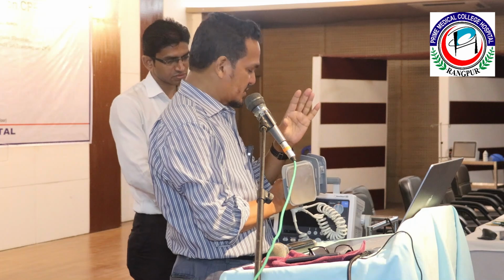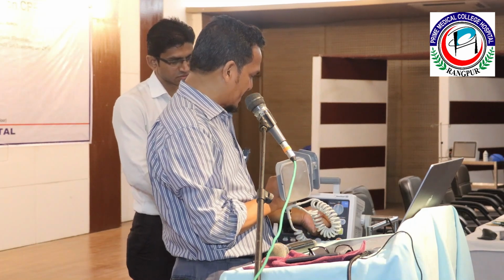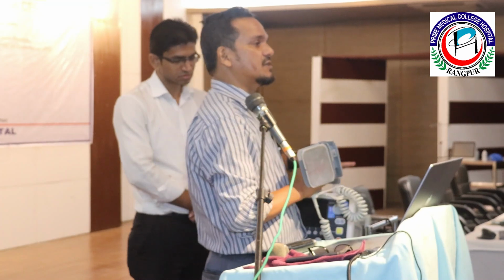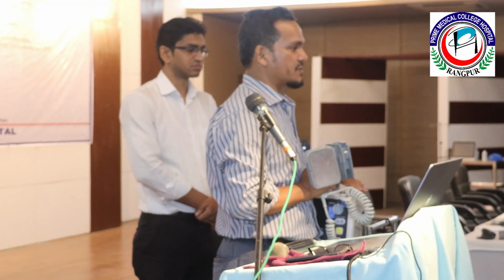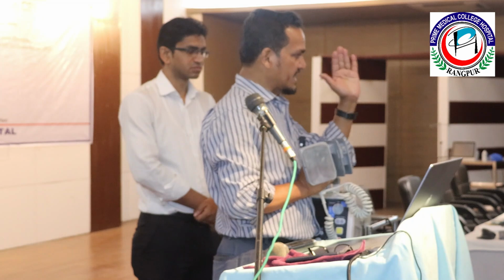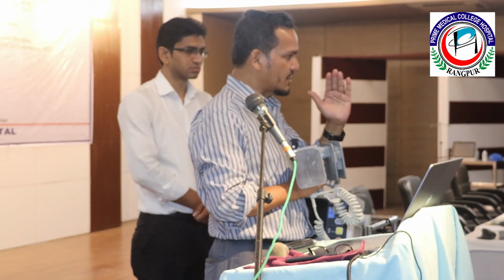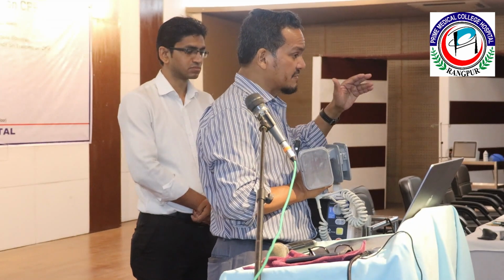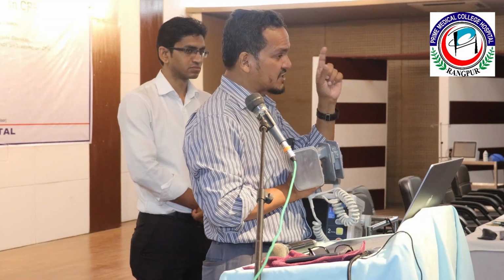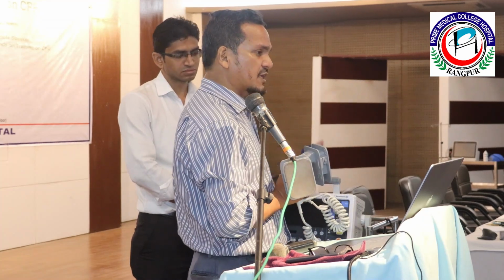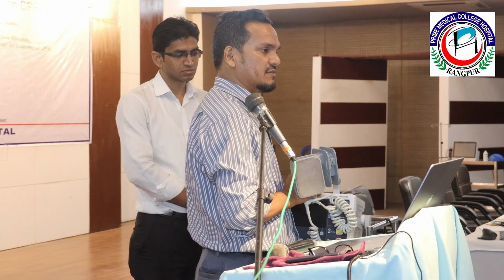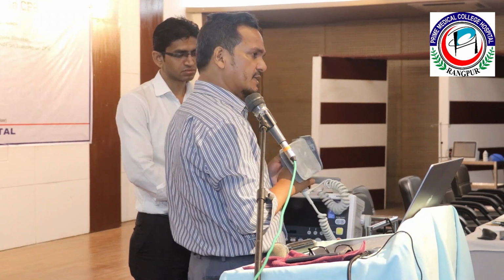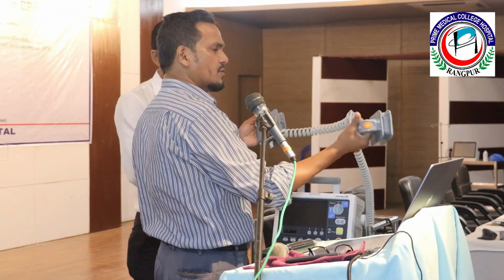Before we give a synchronized DC shock, here is the synchronized button. Press this synchronized button and the machine will detect when to deliver the energy. We use it when we are getting a shockable rhythm and the rhythm is non-fibrillation. In case of ventricular fibrillation, there is no need for synchronized button activation, and in that case, just charge it.